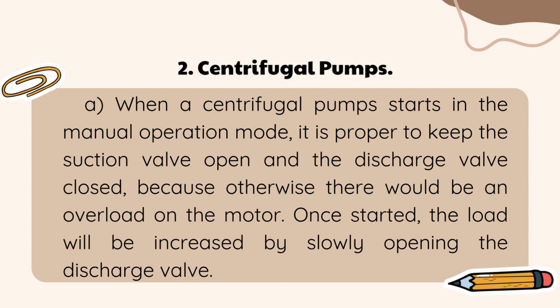2. Centrifugal pumps. A. When a centrifugal pump starts in the manual operation mode, it is proper to keep the suction valve open and the discharge valve closed, because otherwise there would be an overload on the motor. Once started, the load will be increased by slowly opening the discharge valve.